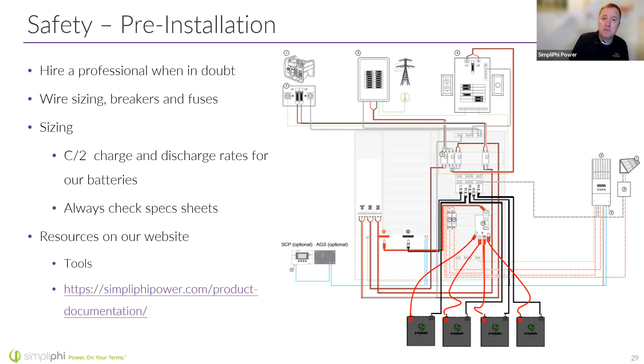Who has put it in the Q&A - who has an insulated torque wrench? That torque wrench is pretty nice up in the corner, I wish I had that one. That's a digital, I believe insulated, torque wrench - maybe it's not, but get a torque wrench out. 160 inch-pounds is what I want to see when you're torquing down our battery lugs. Don't let one of your technicians get the Makita or Milwaukee impact driver and go to town on these battery lugs - get the torque wrench out.